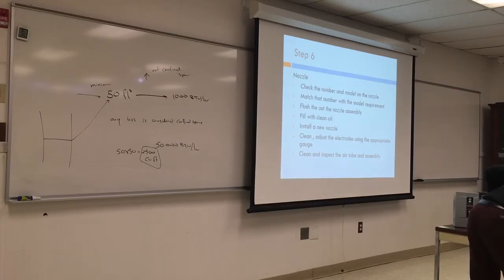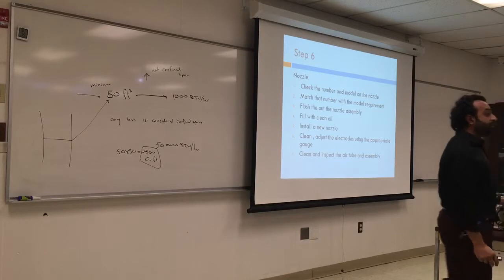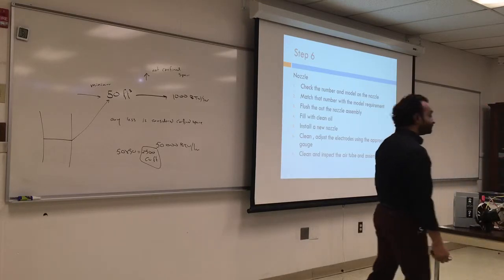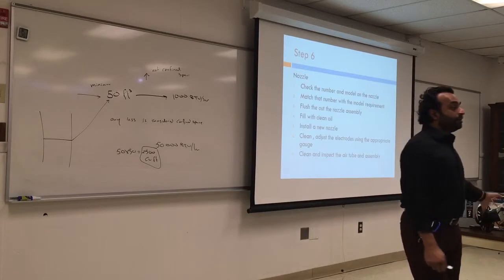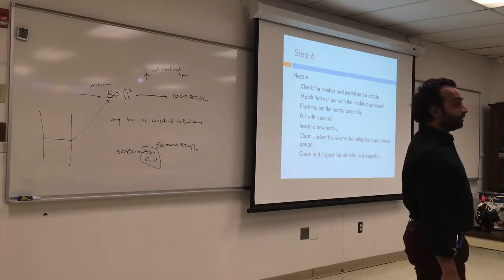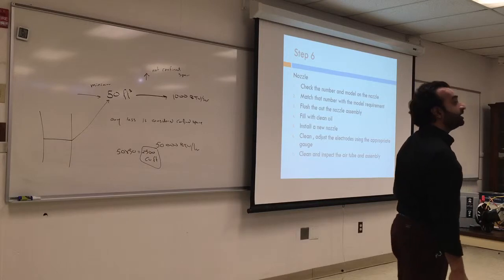So this one should say on it how much. This will tell you the nozzle here. It has the nozzle number and it has the pressure. So the nozzle has 1.35 GPH, and they give the model number specifically with an angle of 85. The pressure is 140. So always follow the sticker on the burner. If you don't have the sticker, what are you gonna do? You're gonna go with the model number and the brand, and you should find something. If it's something older than 20 years, probably just stick with what's in there. You're not changing anything.